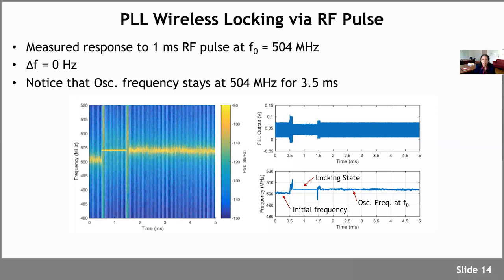We showed that after the initial lock, so this is the initial free running frequency of the oscillator, and this is after the RF signal comes in and we lock. Momentarily there is a shift, but we bring it back because of the correction in the loop. Then the oscillation stays almost reliably constant for the few milliseconds that we need. If we wait longer, of course, the frequency starts drifting.